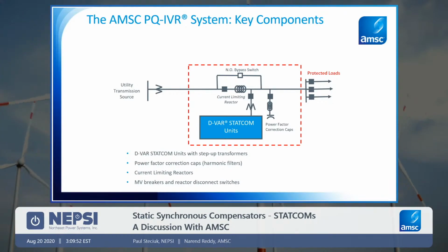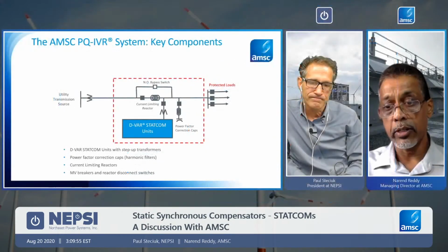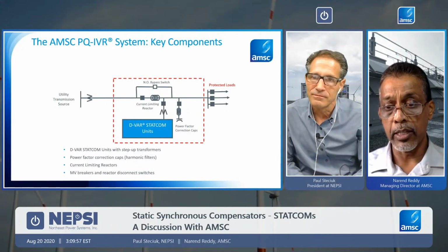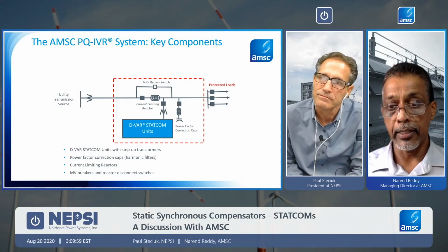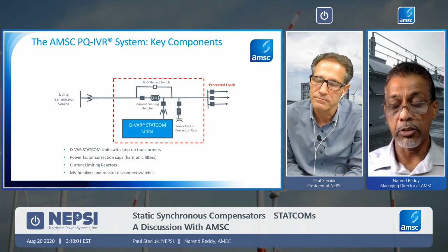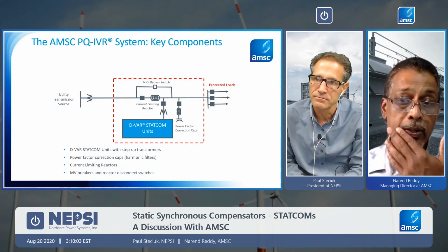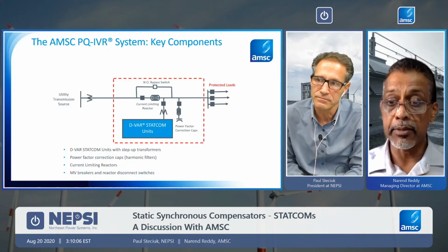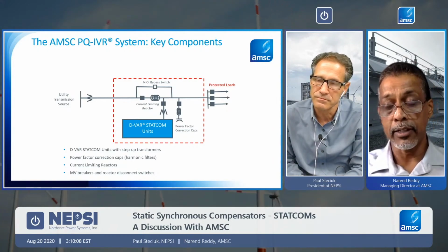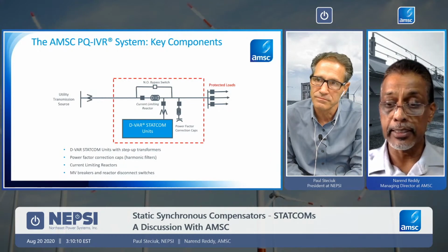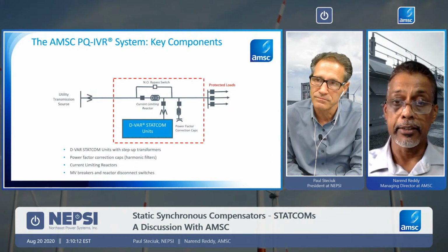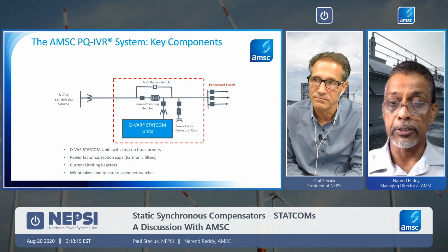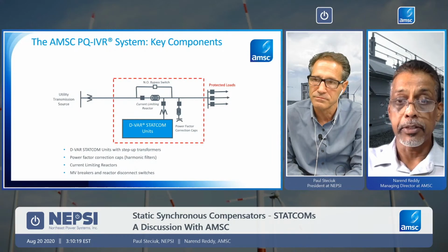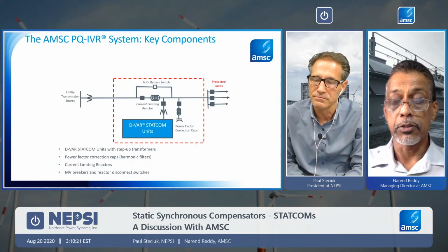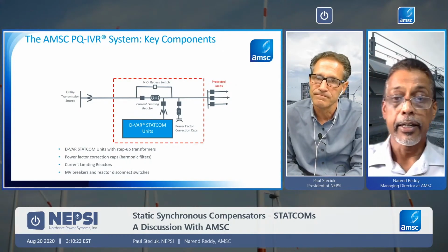Now, these systems are really load dependent, as in how much load they are protecting. Typically, this is a medium voltage installation, so you'd be protecting facility-wide load, and the size of some of these systems for us has gone up as high as about 160, 170 megavars capability, because this is a very crucial part of the business for the facility that's being protected.